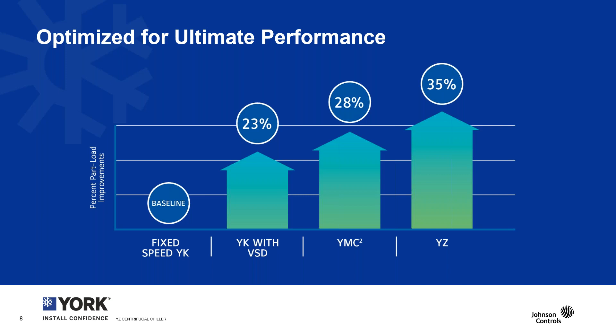But one of the things people have loved about York centrifugal chillers for many years is not just their efficiency, but their broad operating map. The map you see on the screen now focuses on percent load on the x-axis and entering condenser water on the y-axis. This star would represent a typical design point of an AHRI type condition, 44-degree Fahrenheit evaporator and 85-degree Fahrenheit entering condenser water.